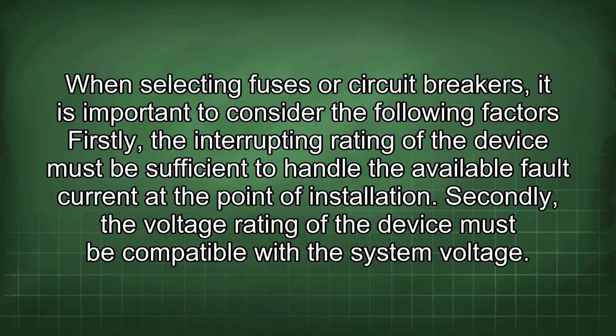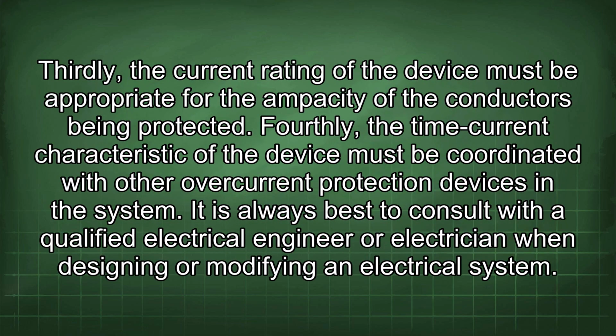When selecting fuses or circuit breakers, it is important to consider the following factors. Firstly, the interrupting rating of the device must be sufficient to handle the available fault current at the point of installation. Secondly, the voltage rating of the device must be compatible with the system voltage. Thirdly, the current rating of the device must be appropriate for the ampacity of the conductors being protected.